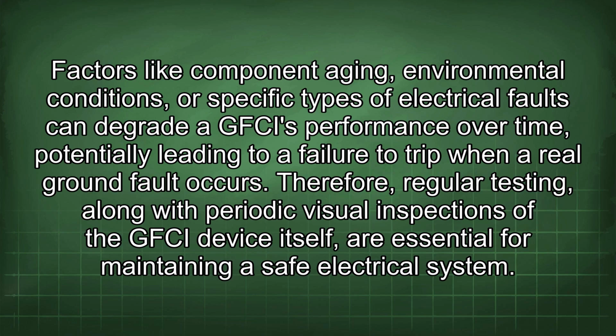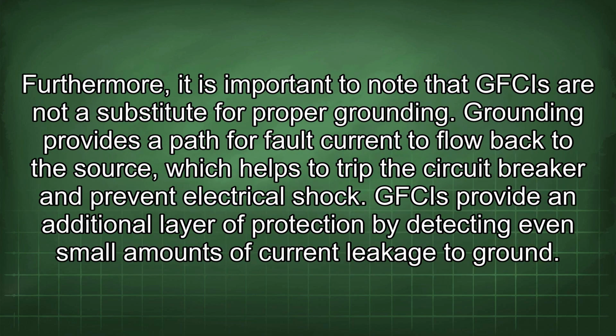Therefore, regular testing, along with periodic visual inspections of the GFCI device itself, are essential for maintaining a safe electrical system. Furthermore, it is important to note that GFCIs are not a substitute for proper grounding. Grounding provides a path for fault current to flow back to the source, which helps to trip the circuit breaker and prevent electrical shock. GFCIs provide an additional layer of protection by detecting even small amounts of current leakage to ground.